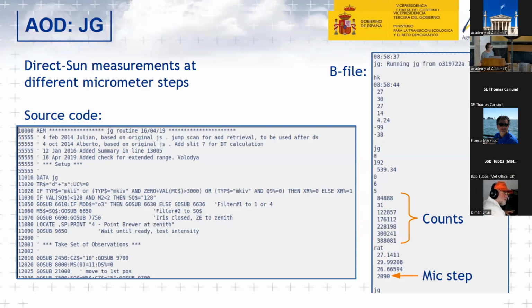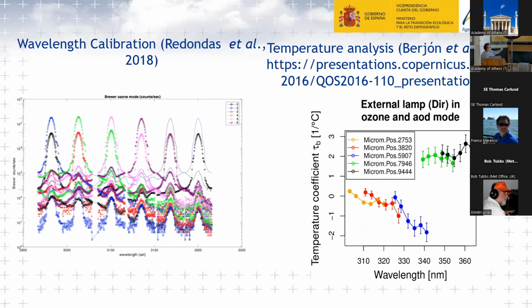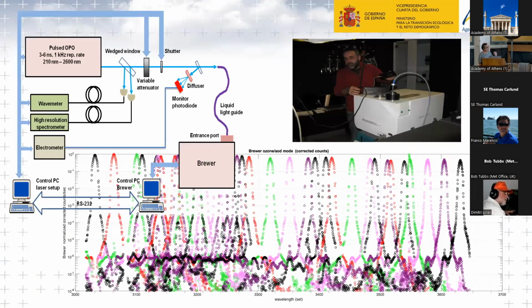We extend the ozone wavelength measurement to include this new measurement, what we call the JG measurement. And this is an example. At the left, you have the slit characterization for the Brewer that we made in that month. Then when you extend the wavelengths, you can go from 310 to 360 and derive the AOD at this particular wavelength. Every color is a different position of the grating. We use all the experience we have. This was during the project where we characterized the reference instrument to transfer the calibration for the AOD. In this case, this is the AOD mode, and you can see all the slits we can measure in the UV spectrum.